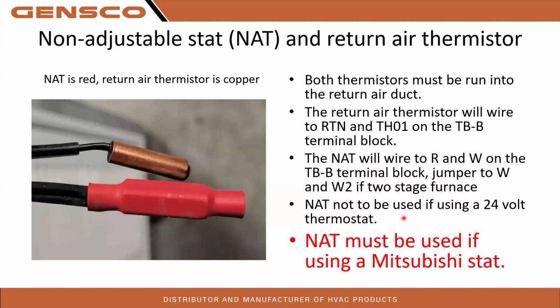If you're using a 24-volt thermostat, so a third-party stat, your Honeywells, Nests, Ecobees, you do not need this non-adjustable stat, because your thermostat will take the place of this, and it's using furnace 24-volt power to power that thermostat. As long as your furnace is still powered on, the stat will be powered up and will work in place of this. But if you're using a Mitsubishi stat, this must be connected.